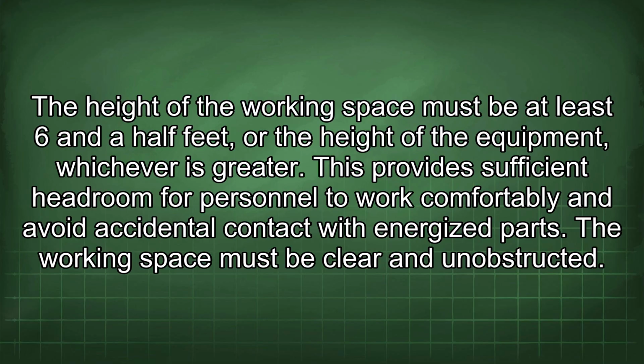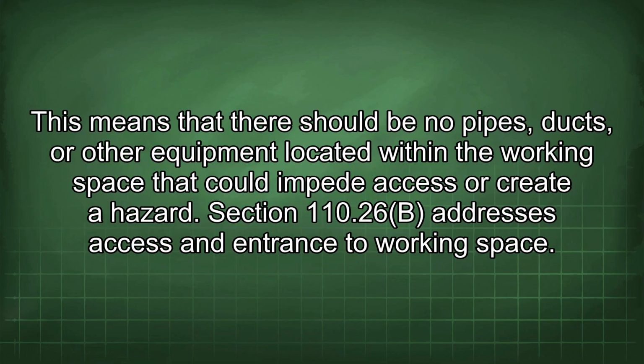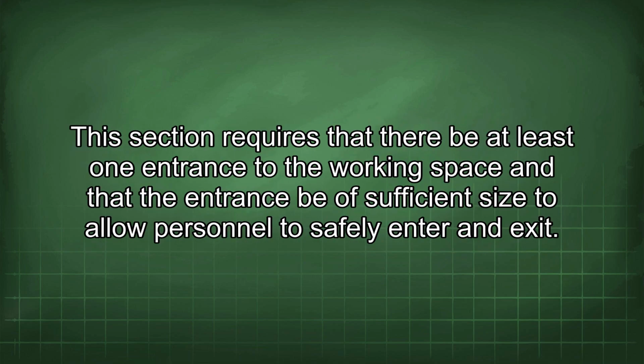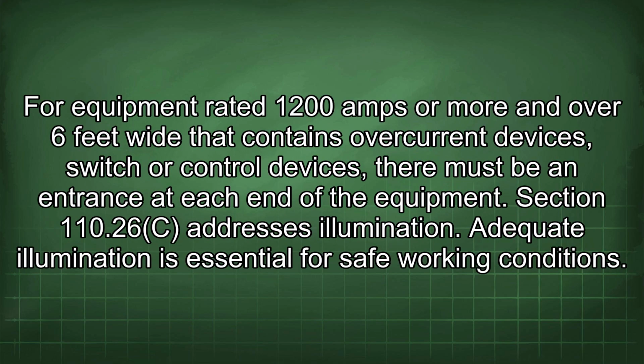The working space must be clear and unobstructed. This means that there should be no pipes, ducts, or other equipment located within the working space that could impede access or create a hazard. Section 110.26(B) addresses access and entrance to working space. This section requires that there be at least one entrance to the working space and that the entrance be of sufficient size to allow personnel to safely enter and exit. For equipment rated 1200 amps or more and over 6 feet wide that contains overcurrent devices, switch or control devices, there must be an entrance at each end of the equipment.